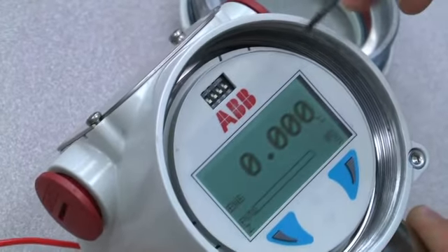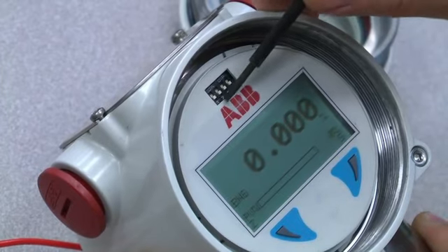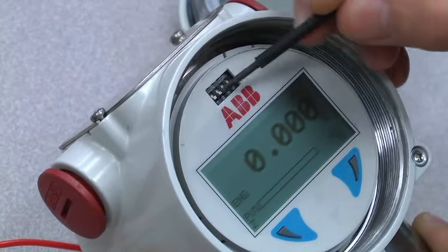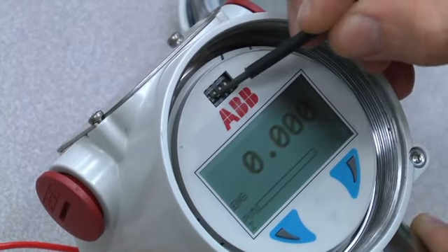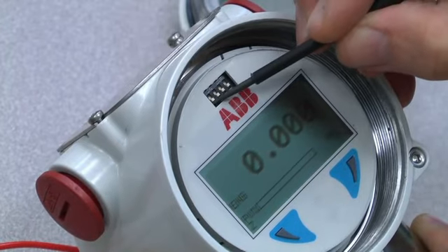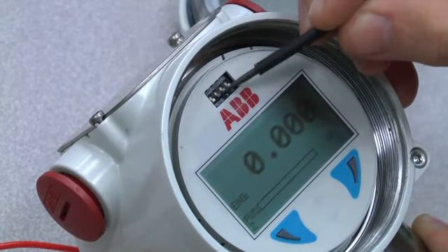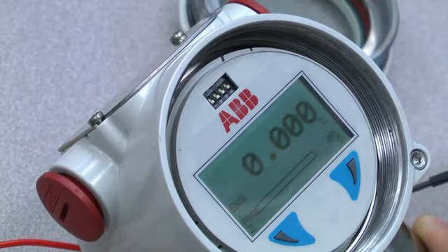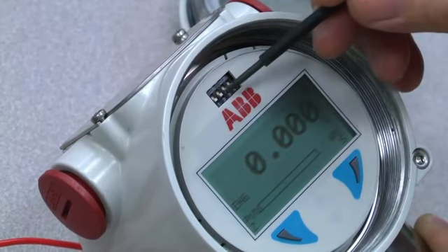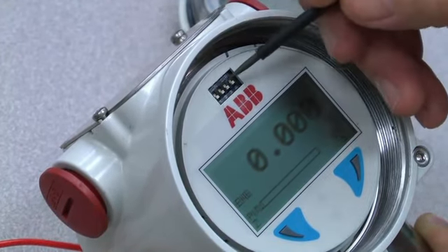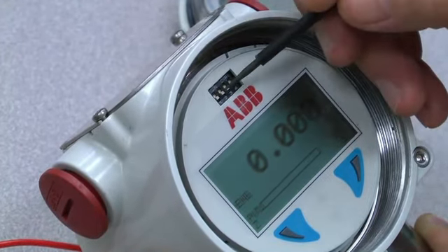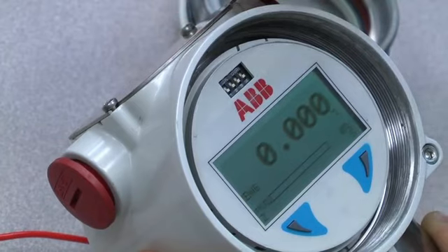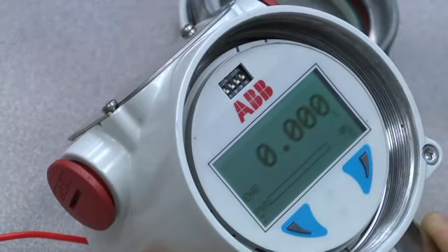Okay, as far as the dip switches go, 1 and 2, they're labeled here, 1, 2, 3, 4. This is in the off position. Up is the on position. 1 and 2 are used whenever there's a replace mode in effect. If you're replacing electronics or hardware, you flip those switches up. Now you want to make sure that the device is powered off when you do that. So anytime you move the dip switches, the device has to be powered off.